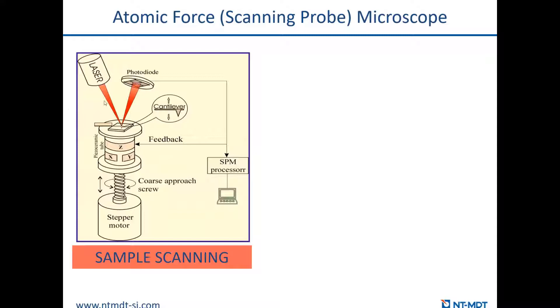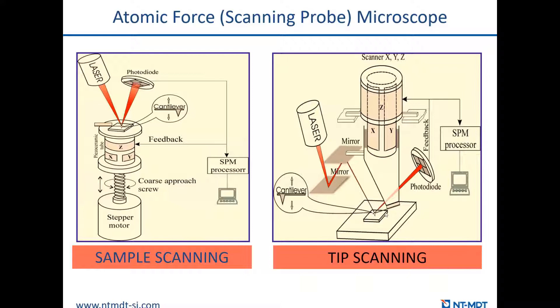First, a few words about how AFM works. We have the sample and the atomic force microscope tip, called a cantilever. We focus a laser on the backside of the cantilever, reflected to a photodiode, and thus we can measure the bending of the cantilever. The bending is directly connected to the force interaction between the tip and the sample. We do atomic force microscopy by positioning the sample under the tip with high precision, or alternatively by moving the tip in X, Y, and Z directions to probe different surface properties at the nanoscale.